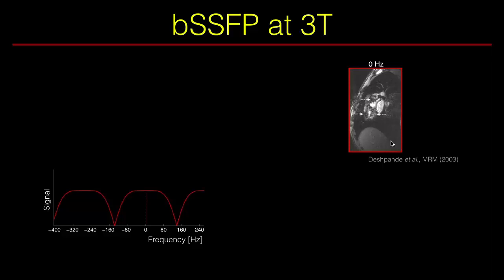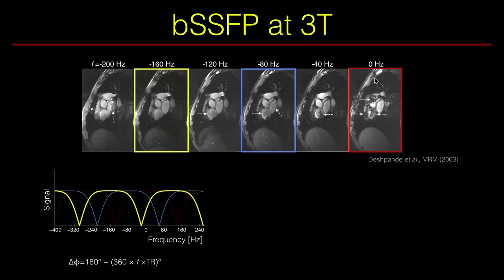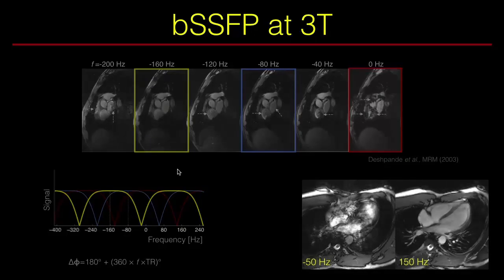Balanced SSFP imaging becomes more complicated at 3 Tesla because field inhomogeneity increases at higher field strength. By shifting the frequency — adjusting the RF phase increment — we can shift the frequency response curve, for example to about minus 80 Hz or minus 160 Hz, moving the bands outside the region of interest. Images show that by shifting these frequency bands outside the region of interest we can get very good balanced SSFP images at 3 Tesla.